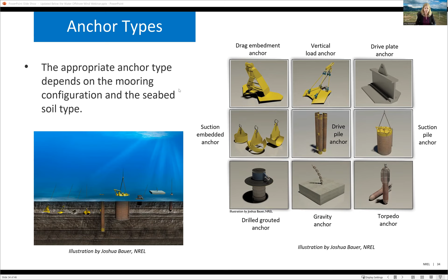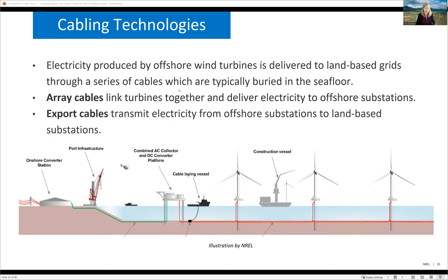Okay, and then cabling, as I mentioned, that we need to obviously get the power from the offshore wind systems back to shore. So we have two types of cables to do that. The first is array cables, which is the cables that used to take the power from an individual turbine to then a common substation for the wind farm. And then we have export cables, which run from that substation for the wind farm back to land to get it back into the larger grid system. And there's different types of cables that are used for those two different types of cables.